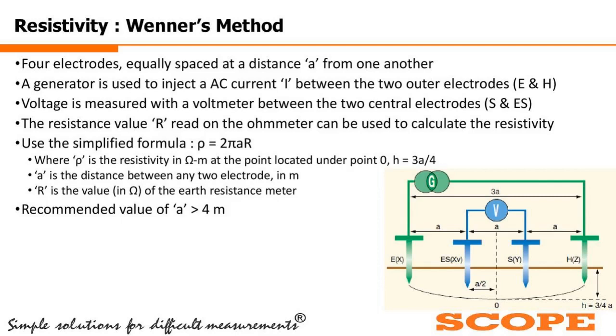Now the only thing we need to take care of is that the distance between two electrodes has to be kept at a minimum of 4 meter. So the distance between two adjacent probes has to be more than 4 meter, whatever the conditions. And you can go up to any distance on the higher side, maybe 30, 40, 50, any distance. Generally, people measure at a distance of 10 meter each or 15 meters each. So A, as a thumb rule, in between 5 to 15 meter can be a good value for the measurement.